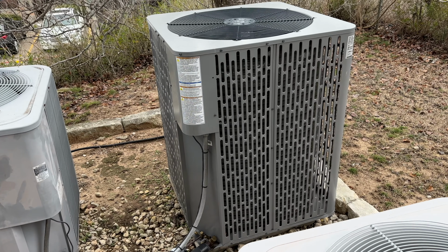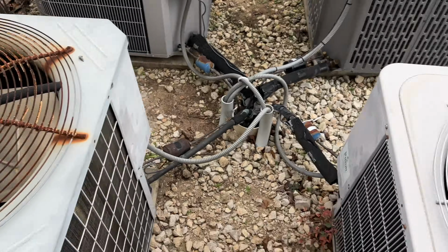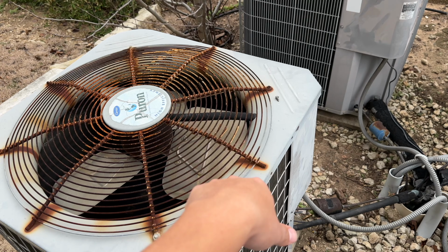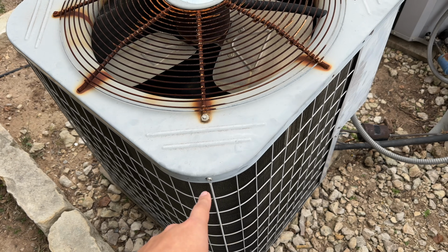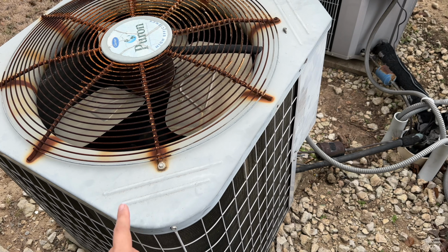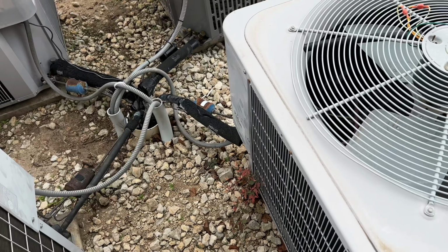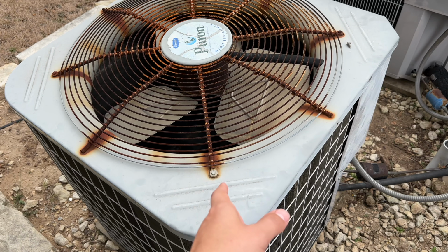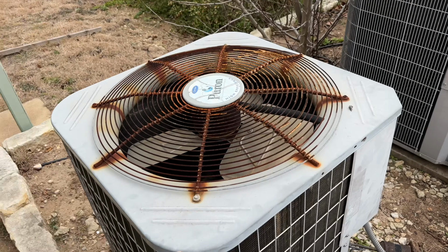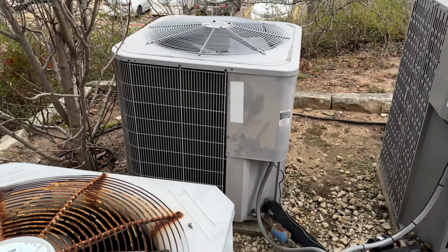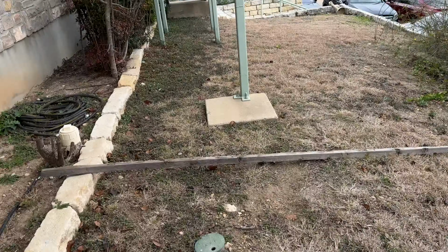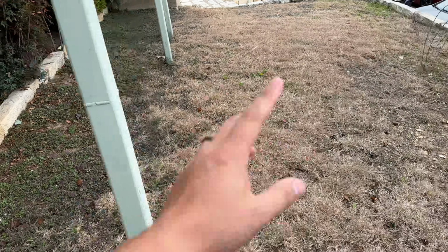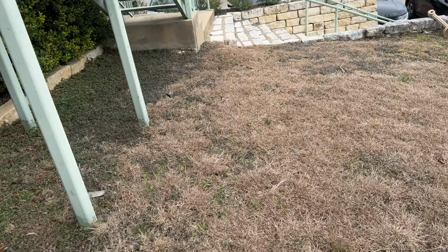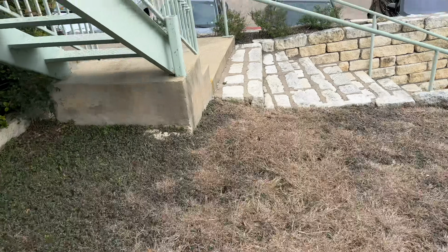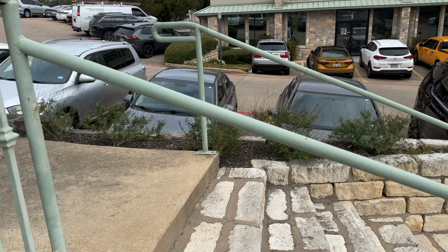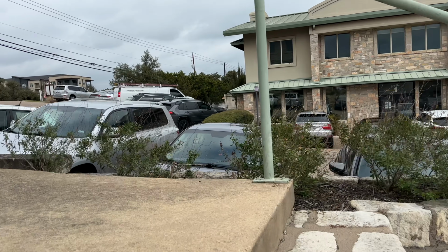We have these split systems. This one's running, and there are 3 more here. I'm assuming it's going to be one of these, maybe this one since it's older. I already went to the attic and saw the air handlers, they looked pretty old, so I'm guessing it's this one, the oldest. The tenant showed me the thermostat, and it was blank. I checked the breaker panel, everything was still on, so nothing tripped at the breaker. I think the issue is at the air handler.